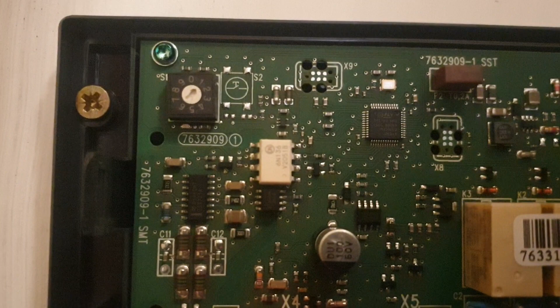There's a little selector switch up here, so you decide which one of these is going to be number one, which is going to be number two, which is going to be number three, so the boiler can identify it. I always put the plug for my common flow sensor in the driver I've selected as the number one driver. So set out to one, that's two, and that's my common flow sensor, the flow sensor for that circuit.